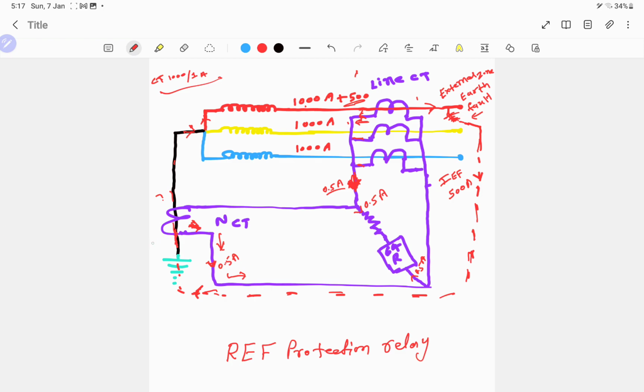So this CT is also 1000 by 1 amp, a 1 amp CT. Because 500 amps is flowing through the neutral CT, 0.5 amp will flow in this direction, through this winding and through here. So now 0.5 ampere here, 0.5 ampere here. The phase angle of this CT is similar, but the value is equal and in the opposite direction, so they will cancel each other.